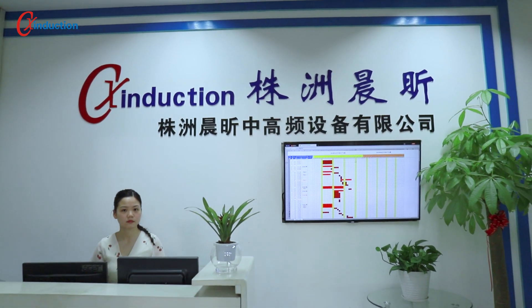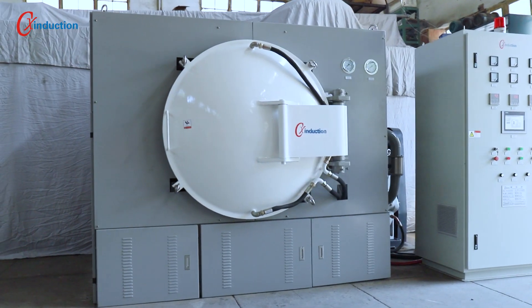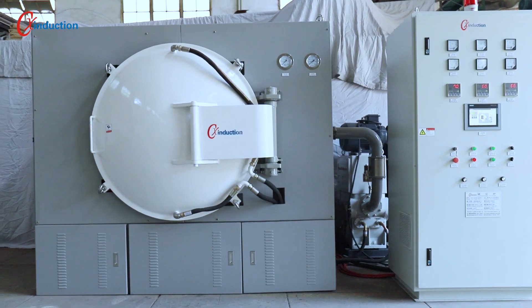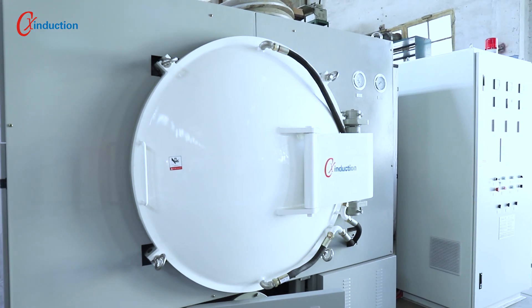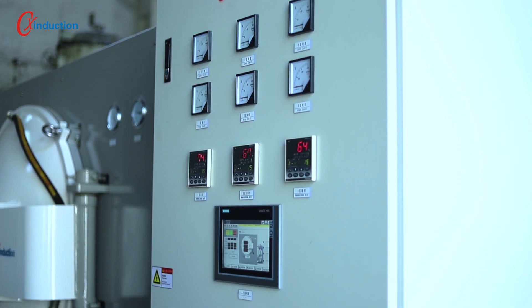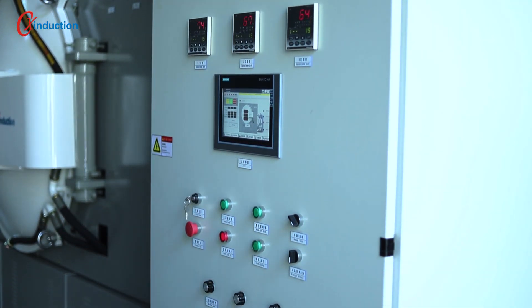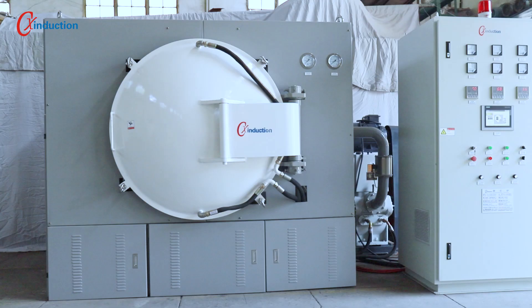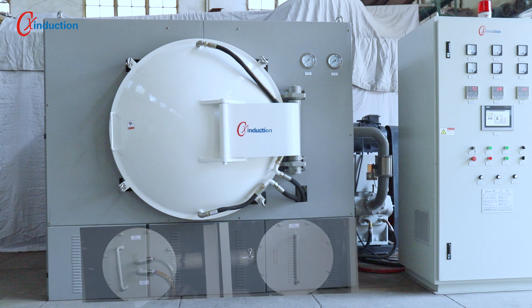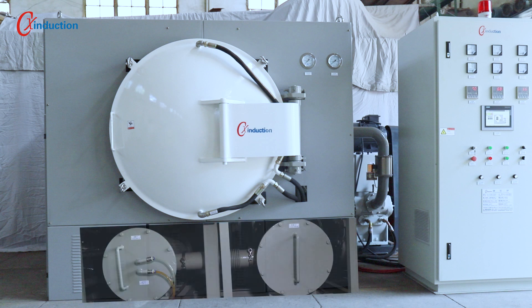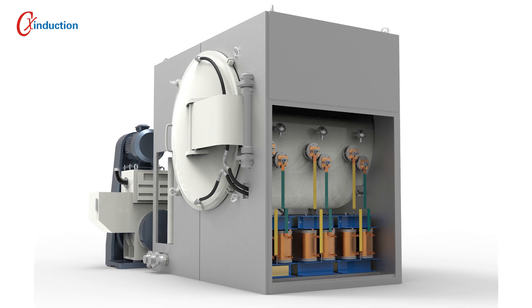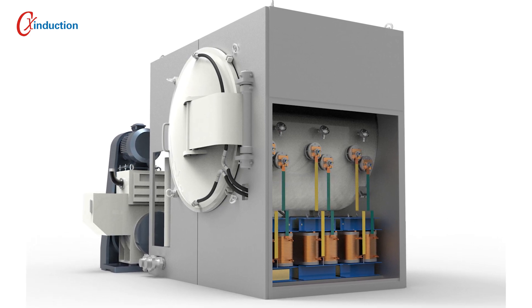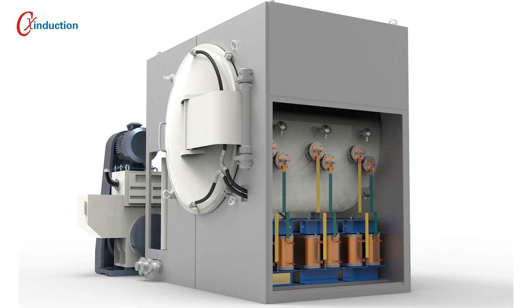Let's introduce a common industrial carbonization furnace. The carbonization furnace is a resistance heating furnace that uses graphite elements. It can heat treat various materials under protective gas, like inert gas, or vacuum. The maximum working temperature is 1600°C, which can meet the carbonization process requirements of various carbon materials. The new design of the tar filtration system can effectively eliminate tar produced during the carbonization process and shorten the maintenance cycle of the vacuum pump.